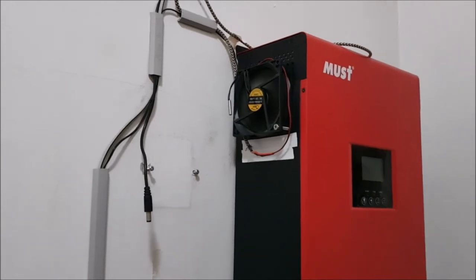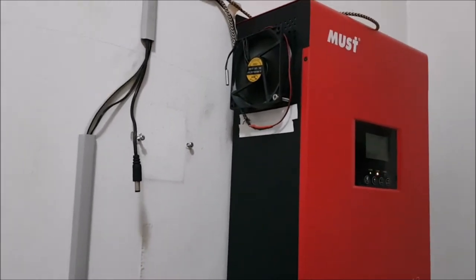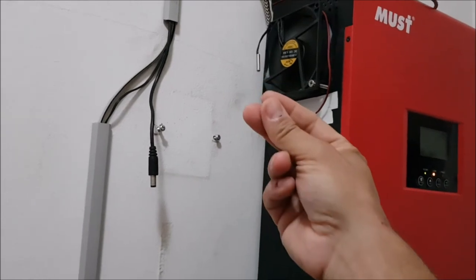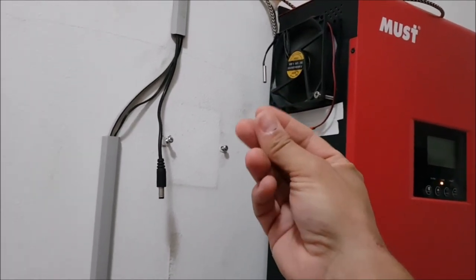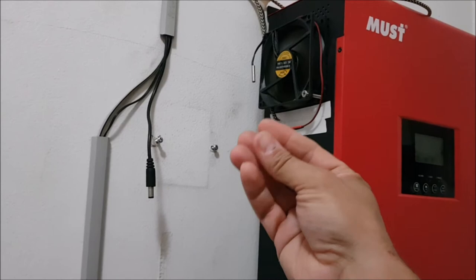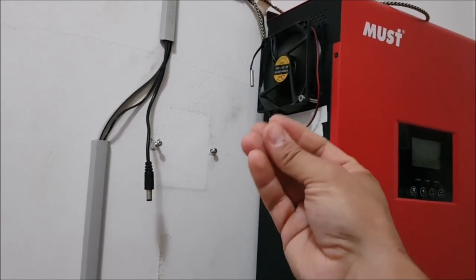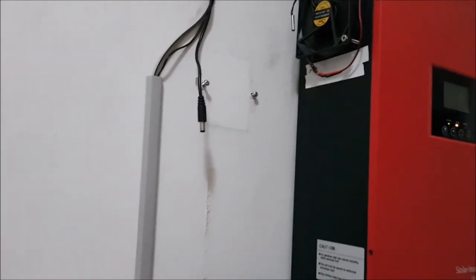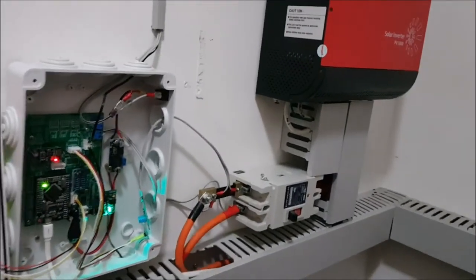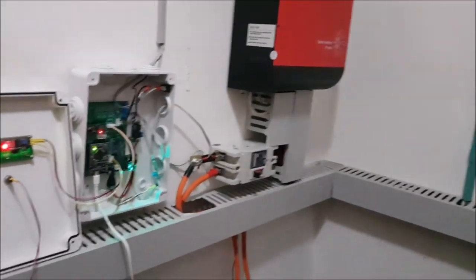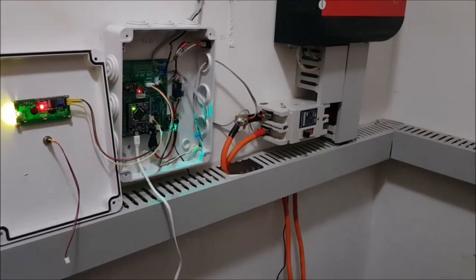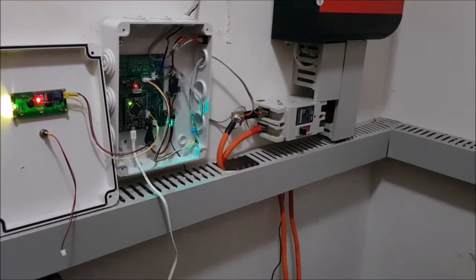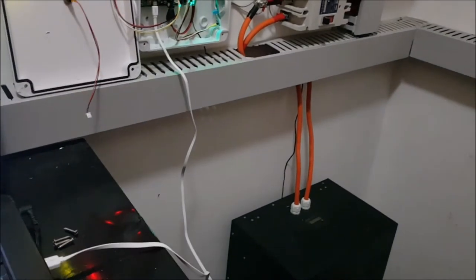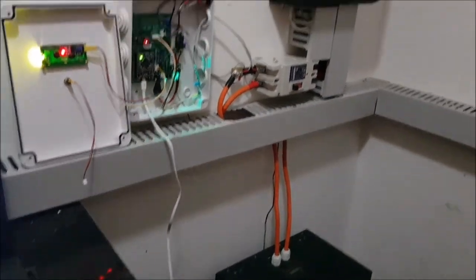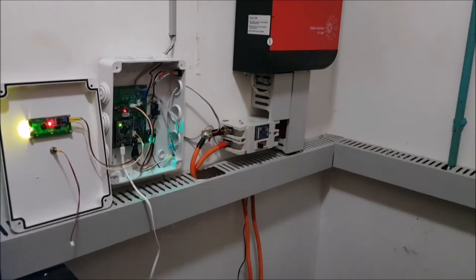So what we will do is we need two known reference points. For the first point, I will hold this sensor until the value does not change anymore, and that will be my 36 degrees Celsius point. And then for the second point, we will use a glass full of iced water, and that one will be our 1 degree Celsius reference point. And in between, it's more or less linear. We can then calculate all the other temperatures.